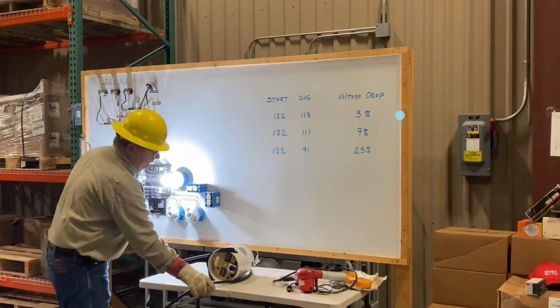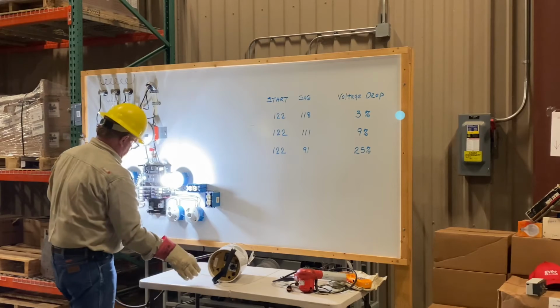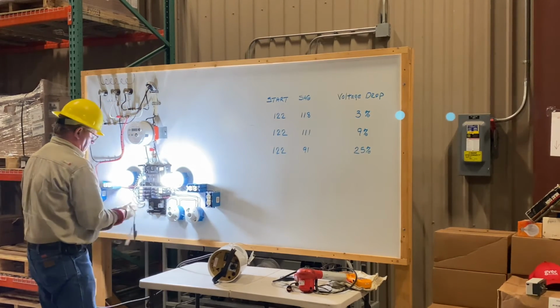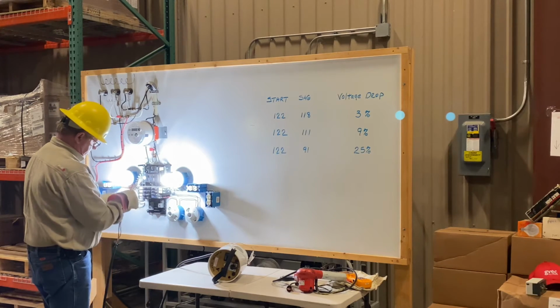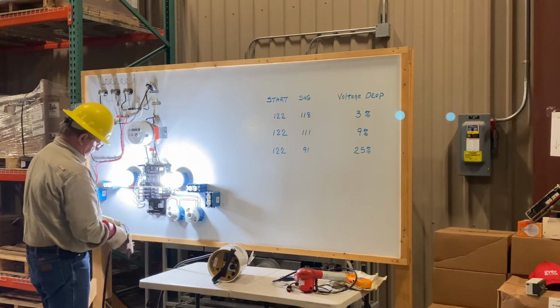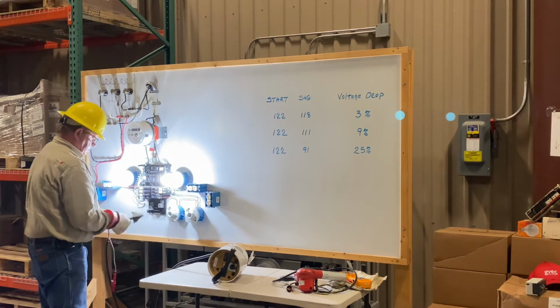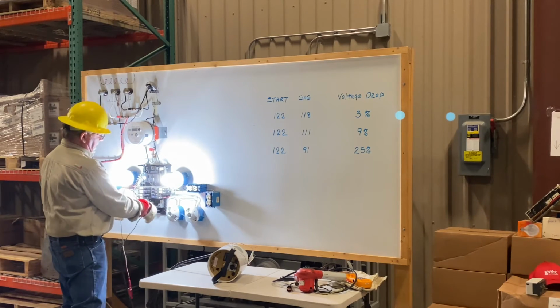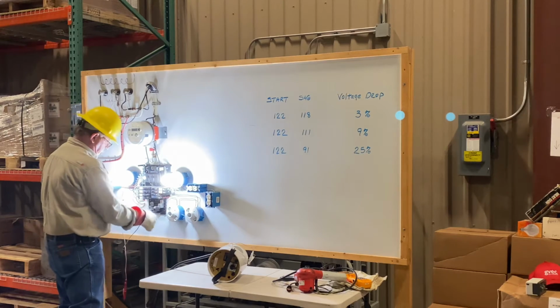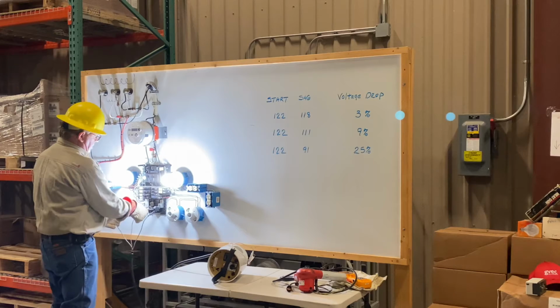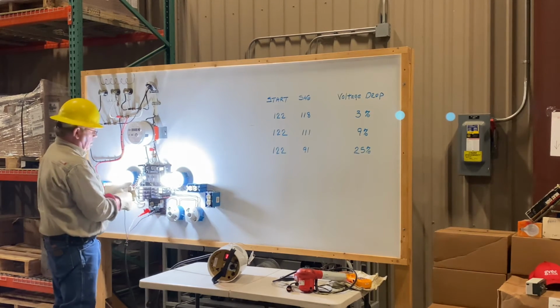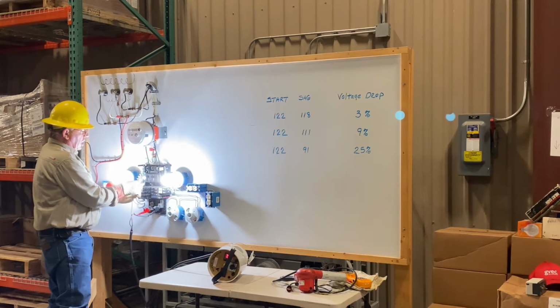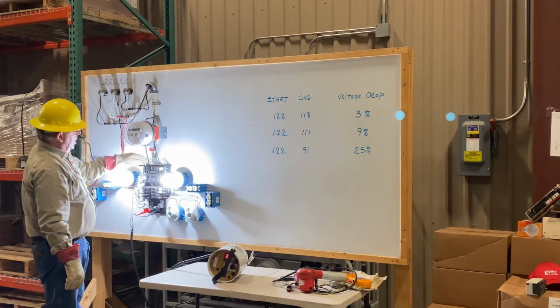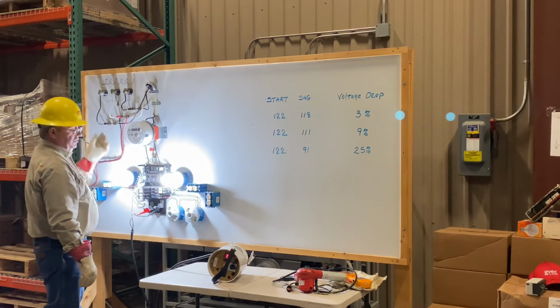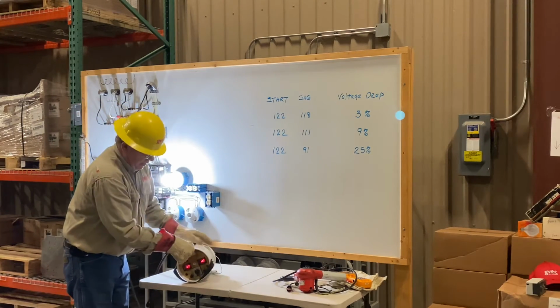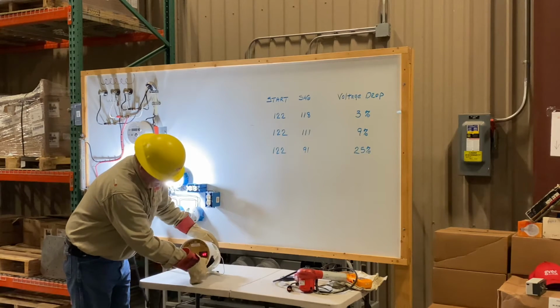You can see here, we're going to take this. Remember, black is right. I like to be down here. That means I've tested everything. Black is right, red is left. Now I have to decide where to connect my neutral. I'm going to connect my neutral to the small bar and force that neutral current to go up through the companion bar, through the lugs, and back to the transformer. Right now, our secondary voltages should be good. I see a balance, 122, 122.